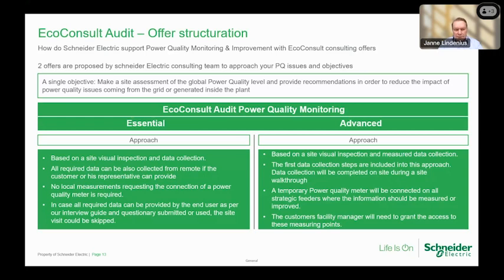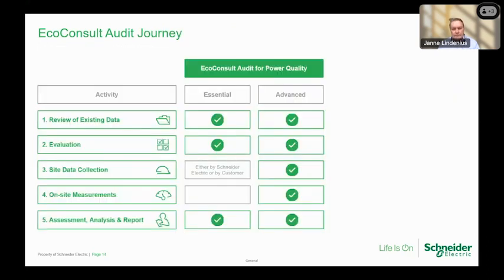The advanced service is based on site visual inspection and measured data collection. The first data collection steps are included in this approach, and the data collection will be completed on site during the site walkthrough. A temporary power quality meter will be connected to all strategic feeders where the information should be measured or improved. The customer facility manager will need to grant access to these measurement points. Next slide, please.